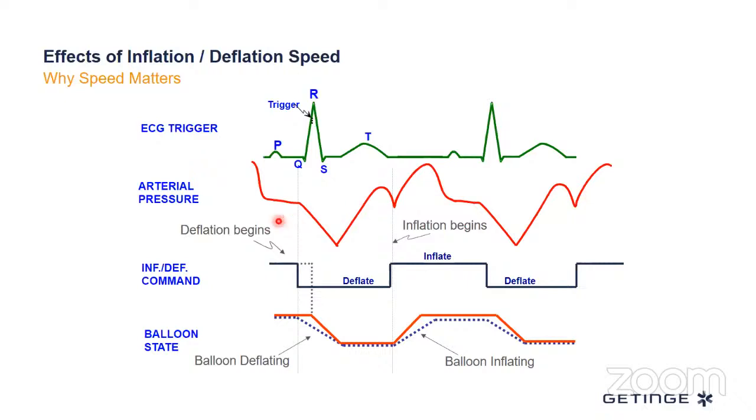And looking at pumps, the pneumatic system on your CardioSAVE is faster than the CS300 or old CS100s because it's a different compressor. Also, with a fiber optic signal, if you get an arterial pressure signal from there, it's faster, it's clearer. So the machine recognizes the opportunity to inflate earlier, and it can actually keep the balloon inflated for longer safely itself. And like I said, the new pneumatics can actively deflate the balloon very quickly. So you have your optimal support during inflation.